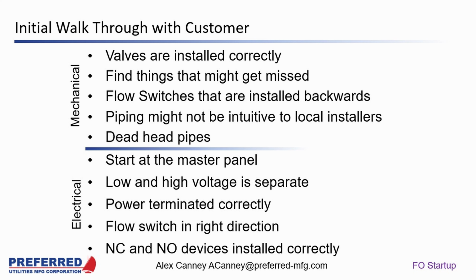Now there are rare cases where you might have a blockage in the return line. I did have one case, the only time I've seen it happen, where a relief valve simply didn't open when tested, at least not right away. It eventually opened, but we had a pump set rated for maybe 50 or 100 psi, and we hit probably 200 psi for about half a second. That was pretty scary. So in a lot of cases, it's just as simple as looking at the entire system, seeing where valves are placed and where the piping runs.